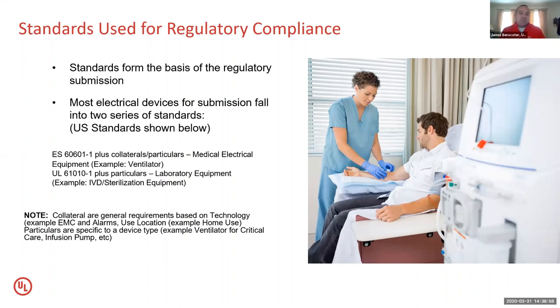First, it's devices submitted that would fall under the standard ES60601 plus its collaterals and particulars. This is a series of standards that provides everything from making sure your device doesn't cause electric shock to the user, electric shock to the patient, all the way down to looking at whether the device correctly reads the amount of CO2 that the patient exhales during use of a ventilator, or whether there's an SpO2 sensor, how well that device will actually measure the oxygen saturation in the blood.